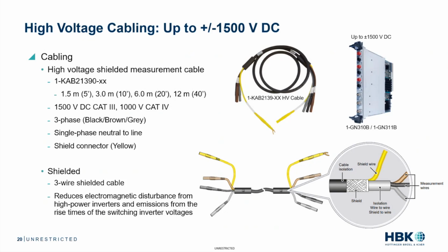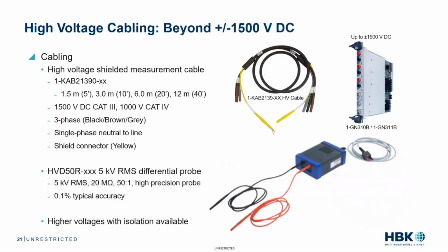So here we have a cable: 3-phase black, brown, gray, the single phase neutral to line, and a shielded connector, yellow. And I want to emphasize that you would only want to connect the shield, the yellow portion of the connector, on just one side of the cable, not both. Otherwise, you would create ground loops. So essentially, just connect the ground on one side of the shield of the cable, and that way you'll create a nice Faraday cage around the cable to reduce the electromagnetic interference.